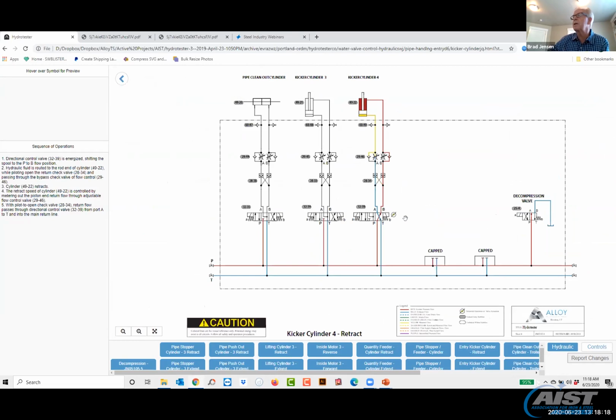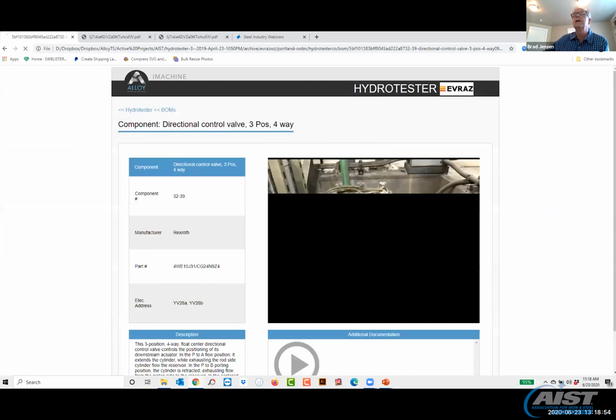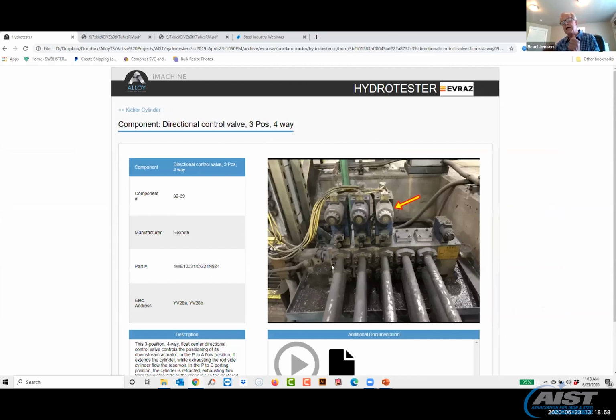So from this, we can look at the circuit and recognize with the color what's happening. We can see that the component, in this case, has shifted, but we don't maybe know what the component is. If you roll over the bubble, we have associated that bubble with the device, which is a directional control valve. And up in the upper left corner of your screen, you should be able to see where we have actually arrowed that directional control valve on the system. So it's one thing to pull the schematic out and begin to follow it, but it's another thing to identify and understand what the components are or what the symbols indicate, and again, where they're located.